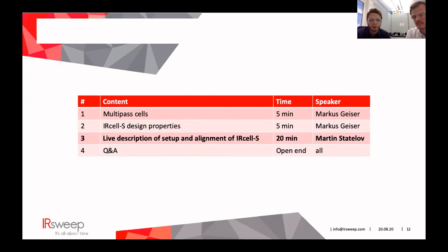We have this in the manual, so if you hit a different mirror as the first mirror, then you will get a smaller amount of reflections, and this means it's a smaller optical path, and we have exact numbers for the path length that corresponds to that. So for example, for the big cell, we have, I think, three different optical path lengths that you can achieve. And you can also go basically straight through the cell, just one pass without any reflection if that is desired.